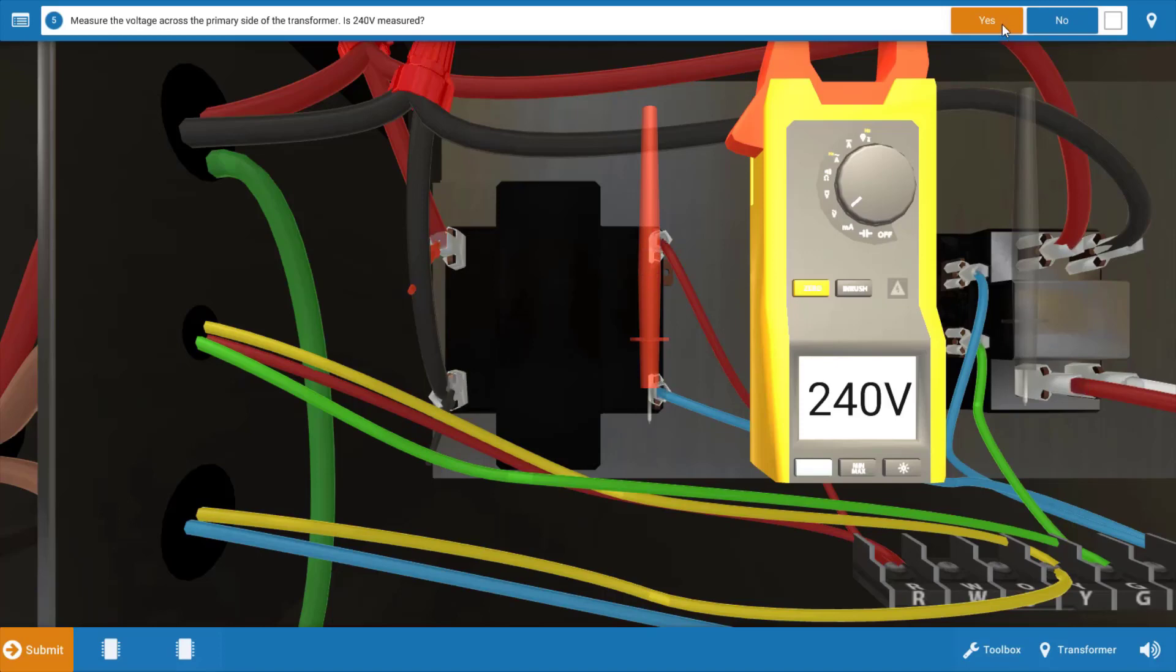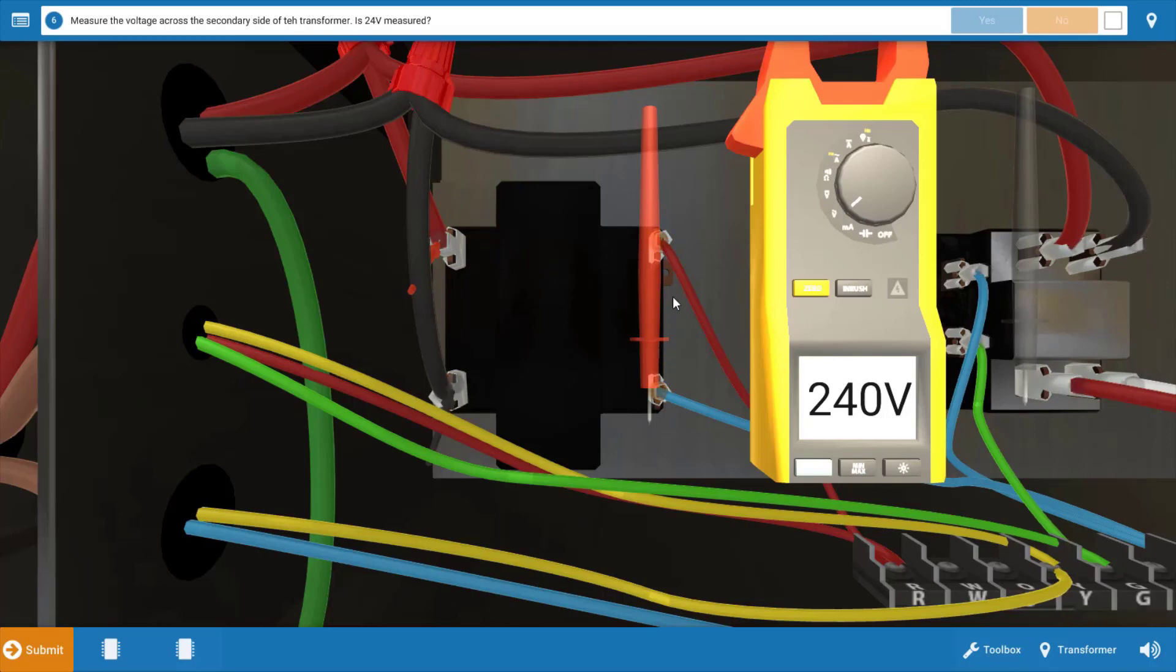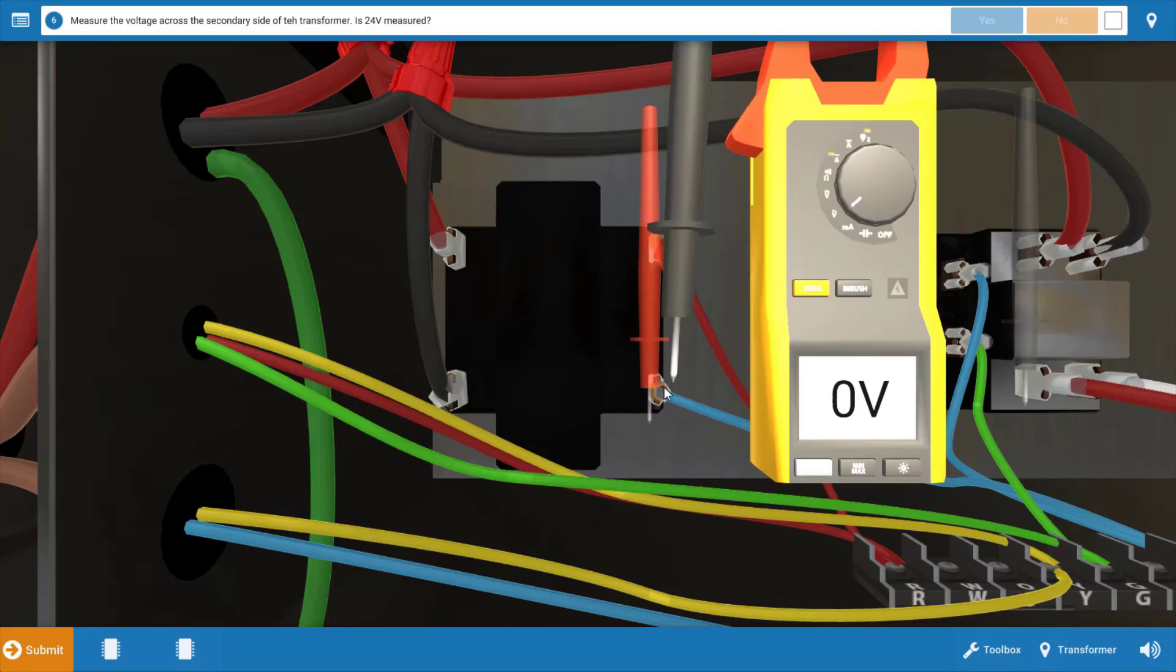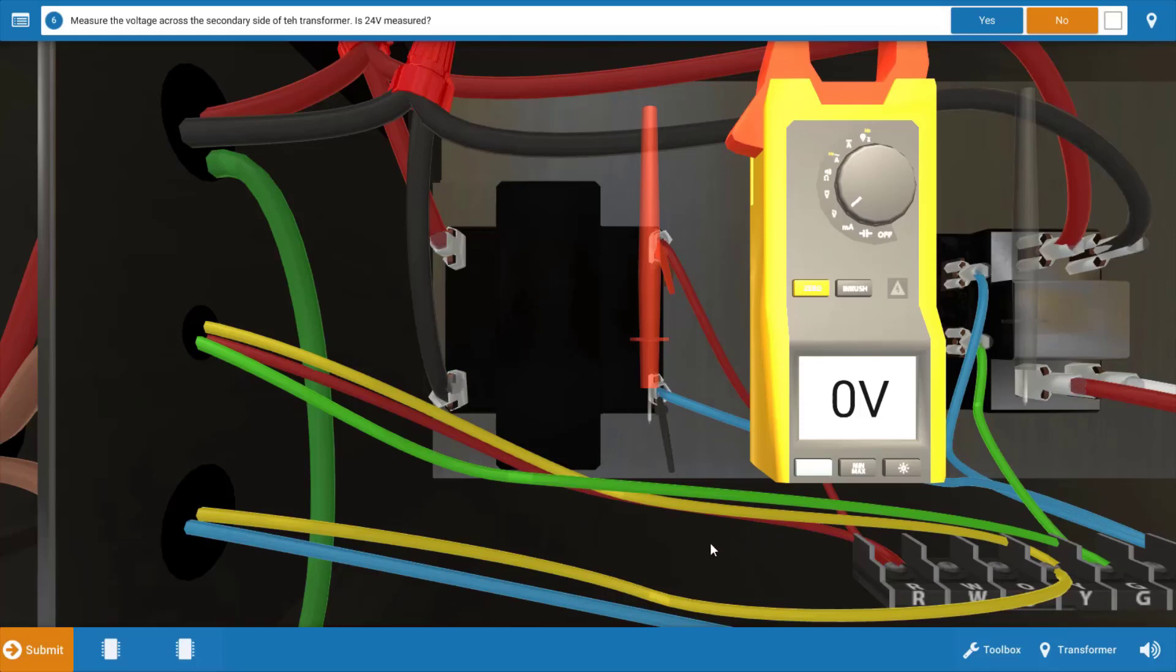So again, click yes on the procedure guide now that we've measured 240, and our next step now is to measure for 24 volts at the secondary of the transformer. So we're going to drop our meter leads on those glowing orange hot spots at the transformer secondary, and when we do this we can see that we have zero volts, meaning we've got power to the transformer but we don't have that control circuit voltage of 24 volts coming out of it. This indicates that the transformer is in fact faulty.